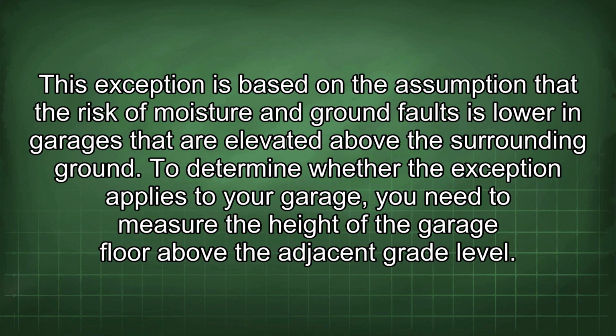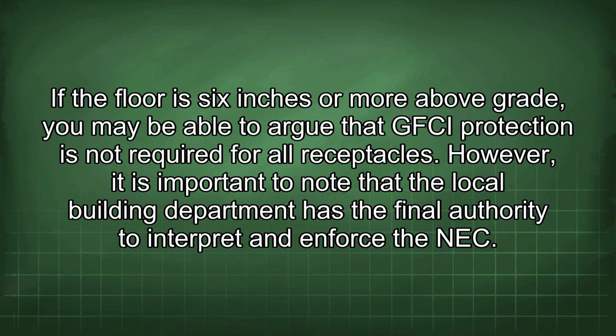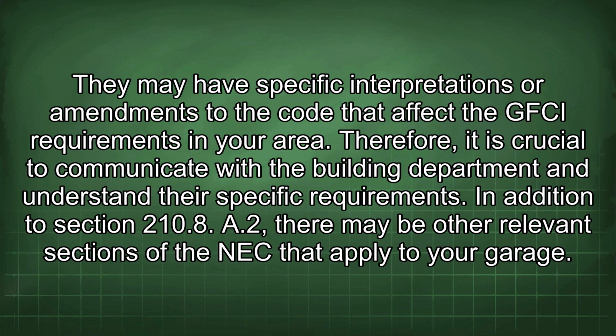To determine whether the exception applies to your garage, you need to measure the height of the garage floor above the adjacent grade level. If the floor is 6 inches or more above grade, you may be able to argue that GFCI protection is not required for all receptacles. However, it is important to note that the local building department has the final authority to interpret and enforce the NEC. They may have specific interpretations or amendments to the code that affect the GFCI requirements in your area. Therefore, it is crucial to communicate with the building department and understand their specific requirements.